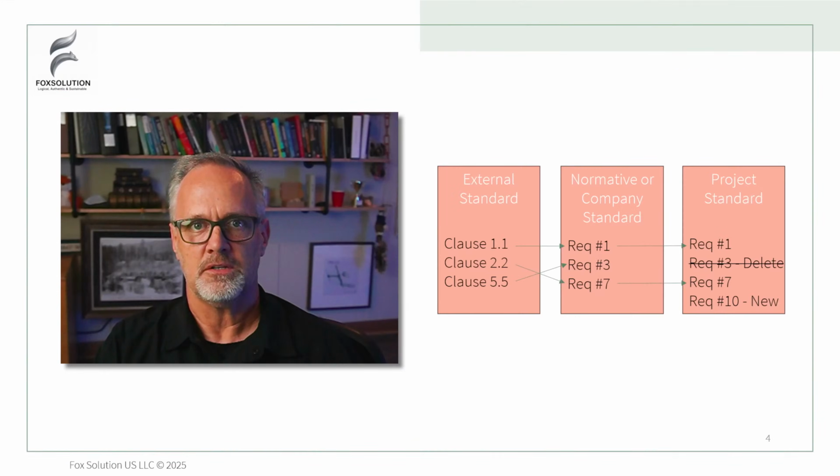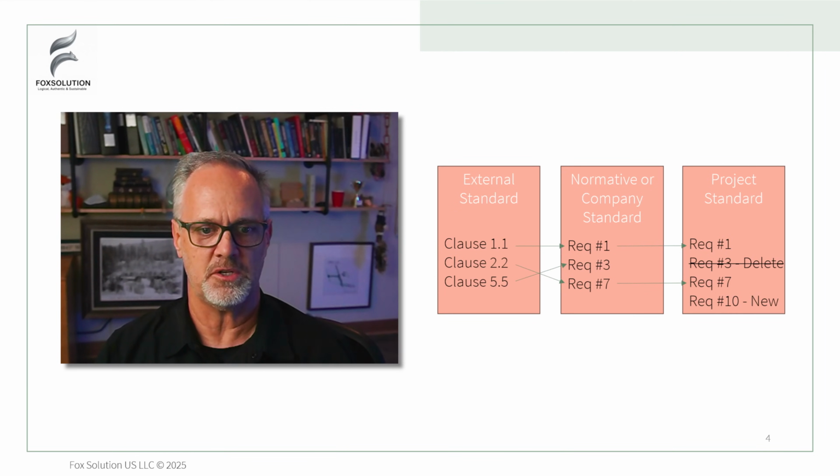So we want to talk not only about what is the logical relationship between the work items, but also what these documents are intended to do and how we are going to use them to drive reuse in our device design. So we have these three different libraries. We have an external standards library. Examples, as I said in the last one: ISO 60601, 11135, or usability documents, or one that was transcatheter heart valve specific in one of the projects that I worked on.